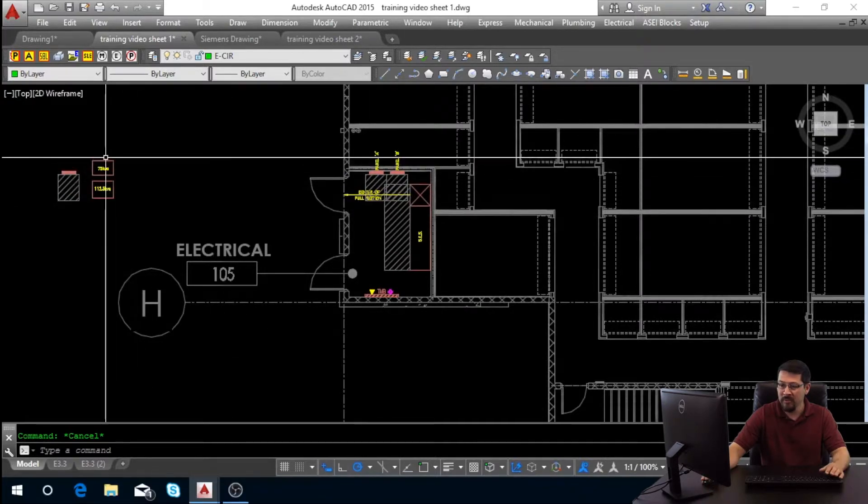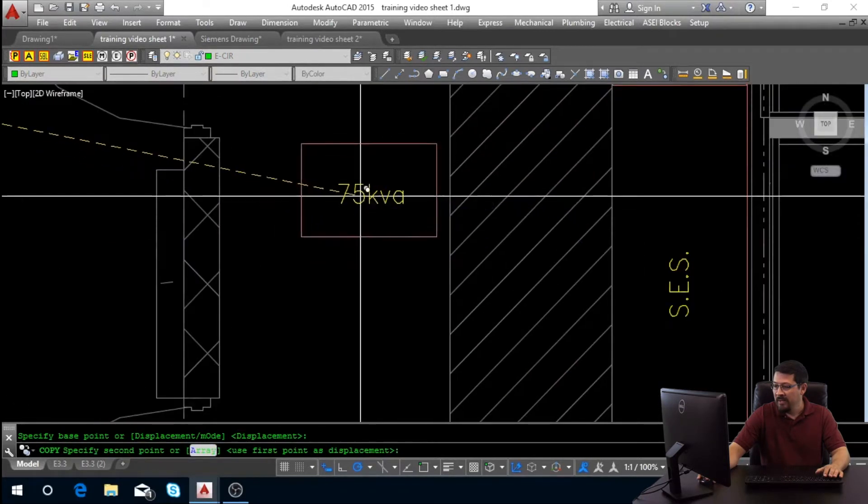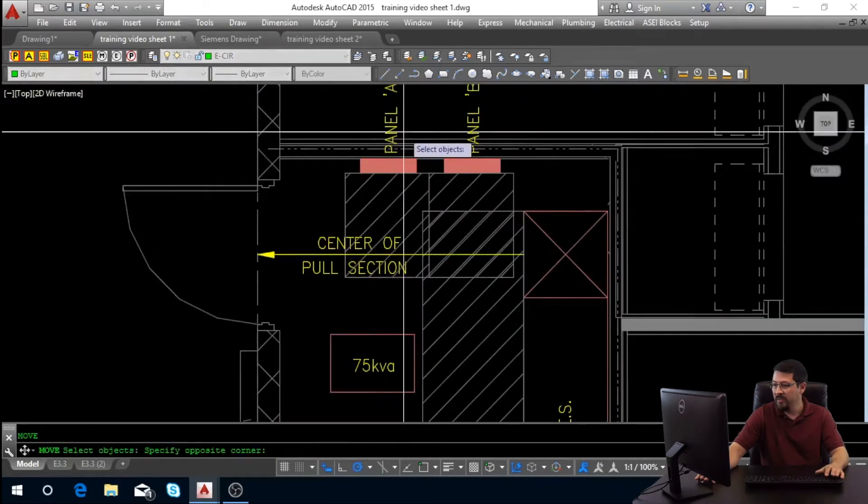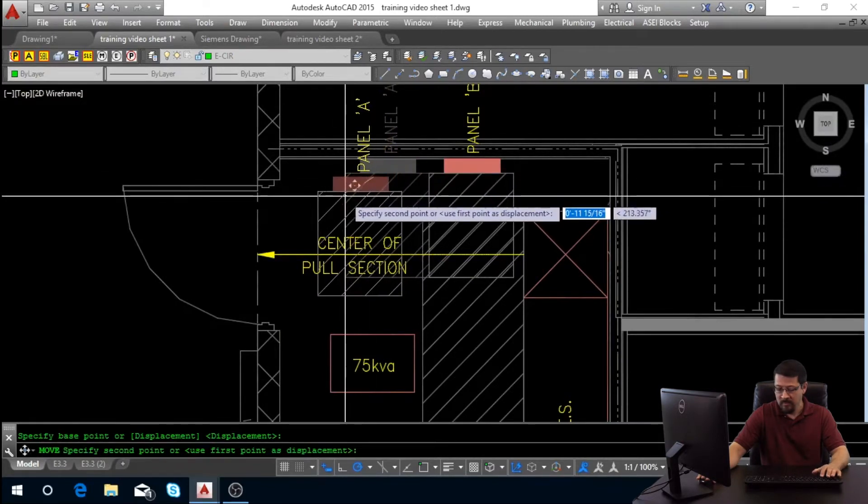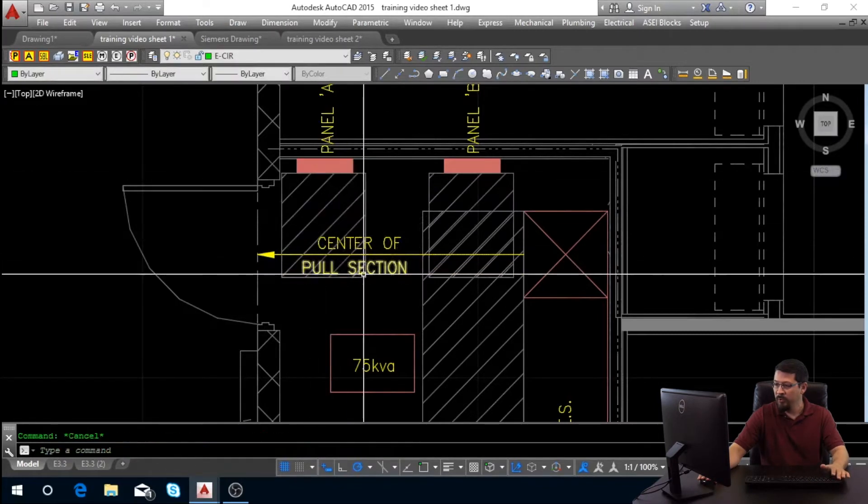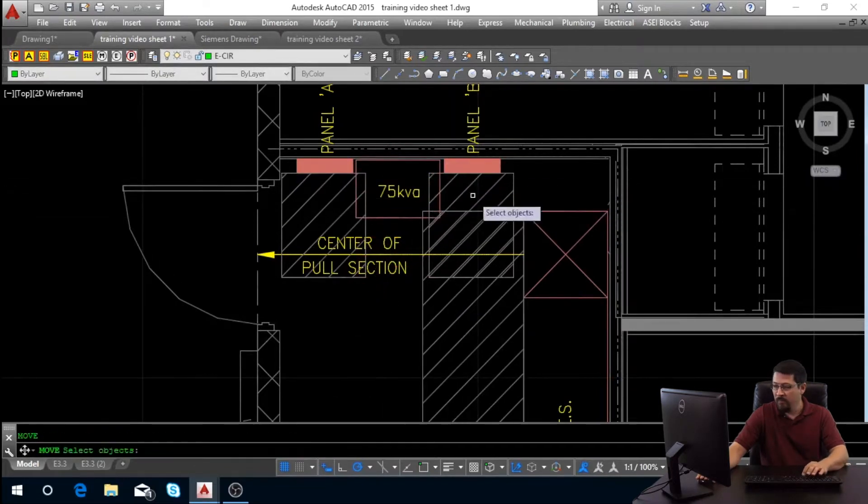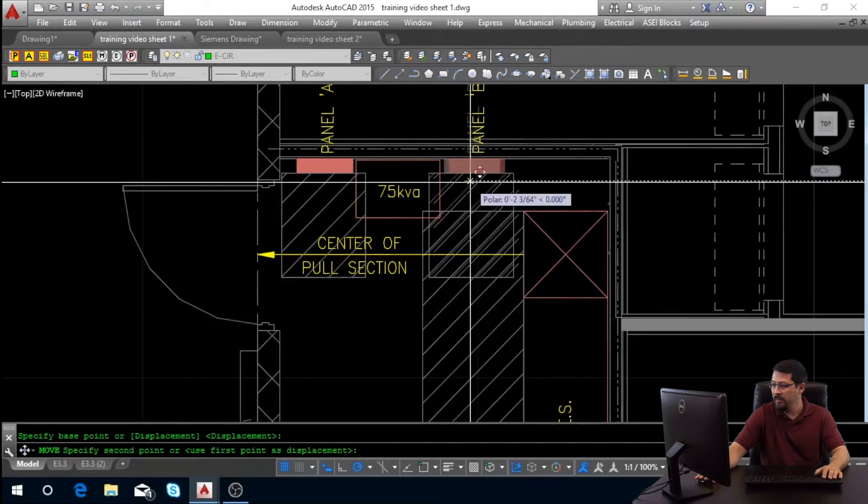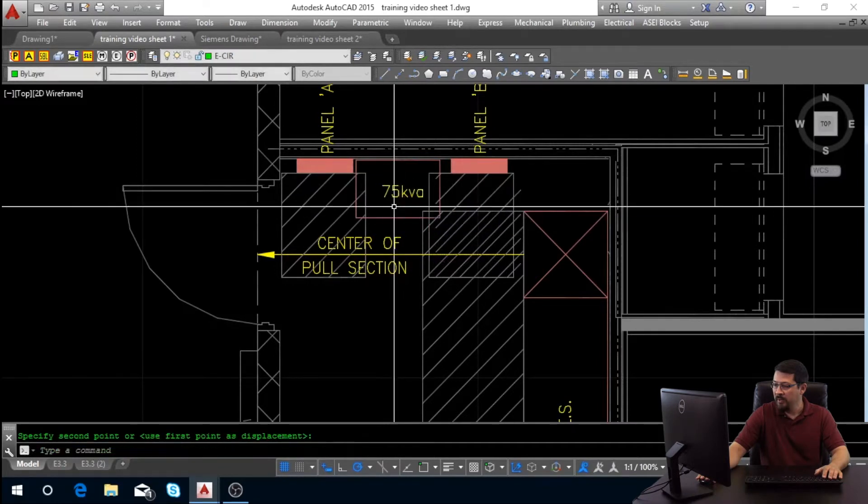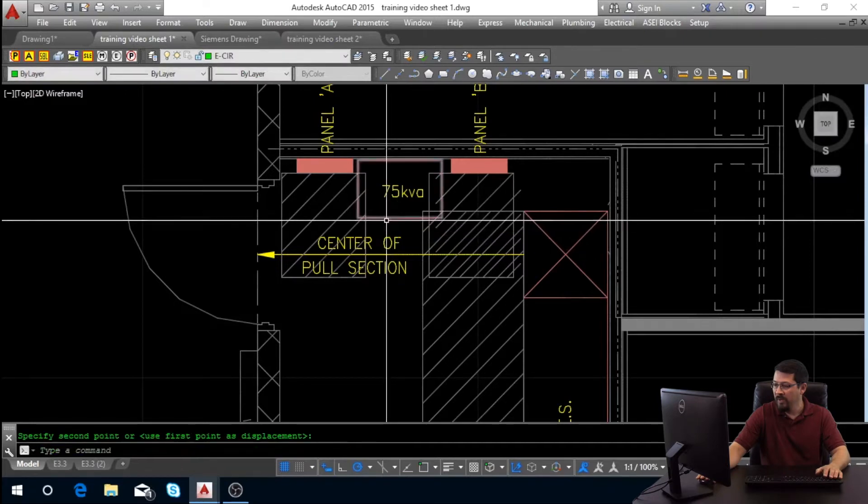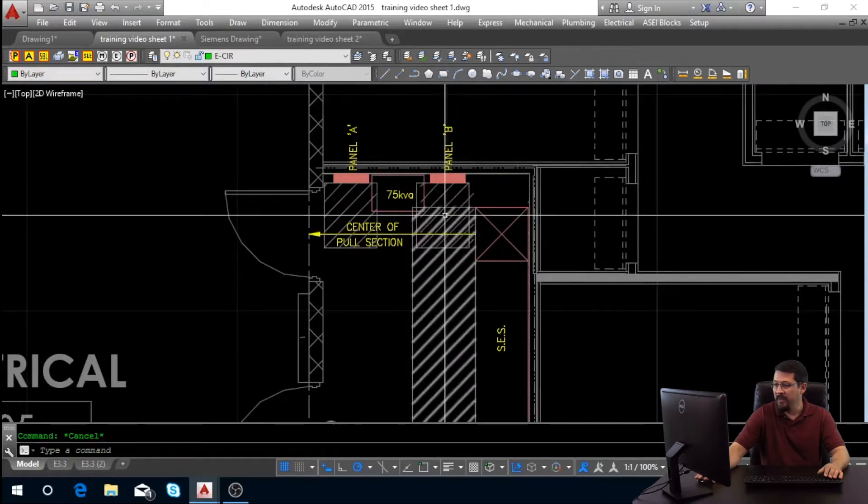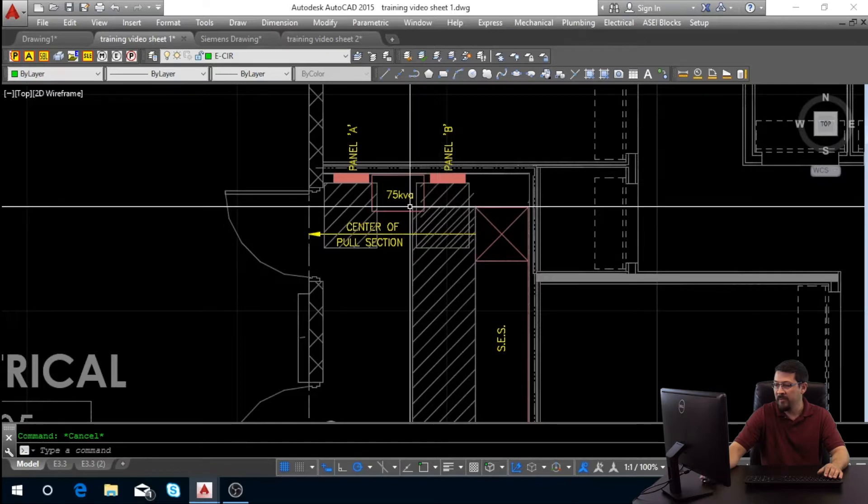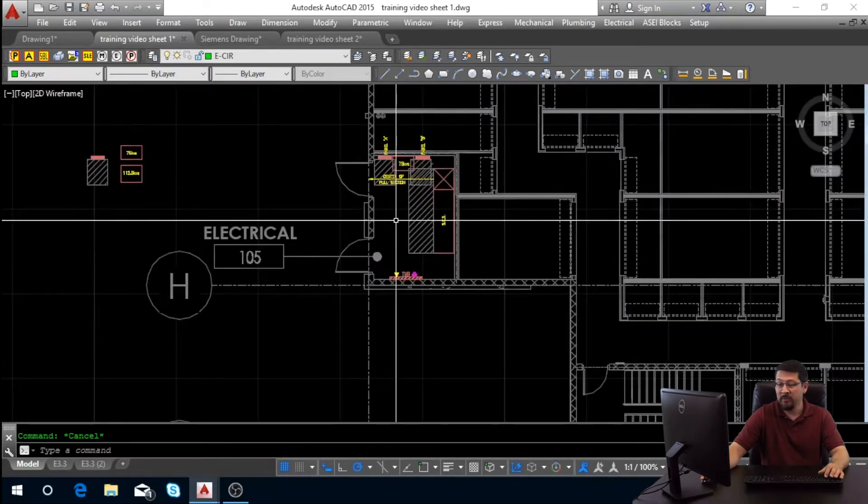If you have a transformer, we can drag and bring that guy in. Bring that over here and move this panel over a little bit. Bring your transformer up and probably move this panel over just a little bit so we still have plenty of room. You just need to make sure that nothing is in front of the transformer, that it has a clear path in front of it. Like we have here. And it can protrude a little bit into those clearance spaces as long as it's not in front of any of the panels. And that's it for an electrical room.